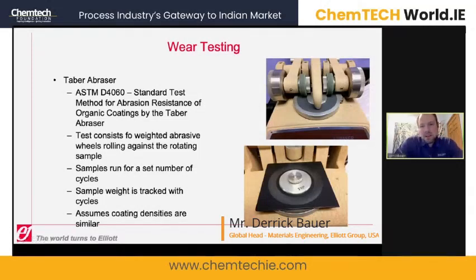Another factor in developing a coating is we looked at the durability of the coating, essentially by doing wear testing. For centrifugal compressors, they are expected to run for anywhere from 5 to 7 years in most applications without a shutdown. Hydrogen recycle compressors typically see 3 years or so, and certainly refineries would like to increase that time in between shutdowns.